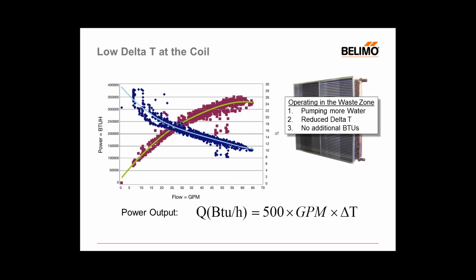So when we get to an area where we can produce the same amount of BTUs for varying volumes of water, we have an opportunity to use less water if we can control to specific parameters. And so that's why we're going to look specifically at delta T and try to make decisions about how we control water through that heat exchange device, because delta T is a fabulous indicator of the efficiency of the heat transfer.